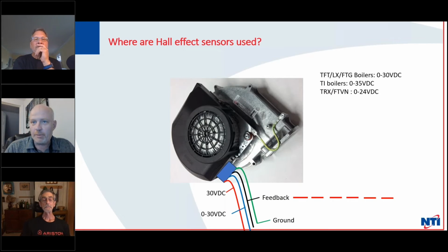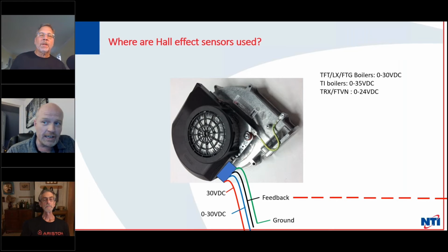And because it's not spinning, you get intermittent hot water calls or no hot water calls. You know, it's funny you say that. That's recently come up, Dave, with the recirculation loops. Yeah, we put out a bulletin about it because we were noticing in tech support that every time someone called with a recirc, the flow meter was wearing out prematurely. So if you do use a flow meter, guys, put a timer on it, put a temperature activation on it, but preferably don't run it 24/7. And if you do, you probably are going to end up having to replace that every couple of years.